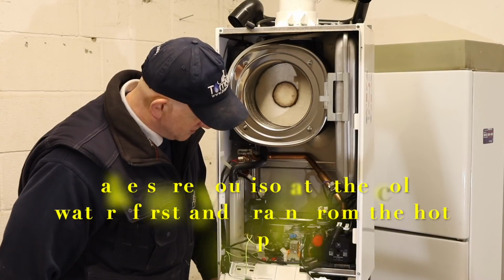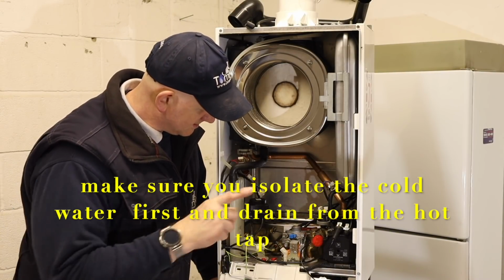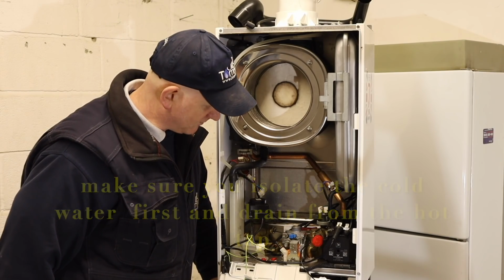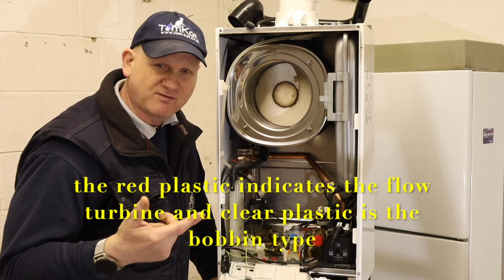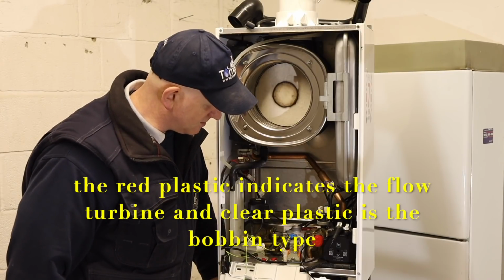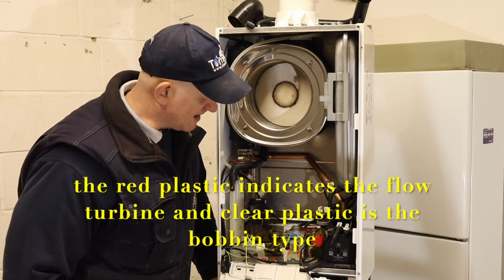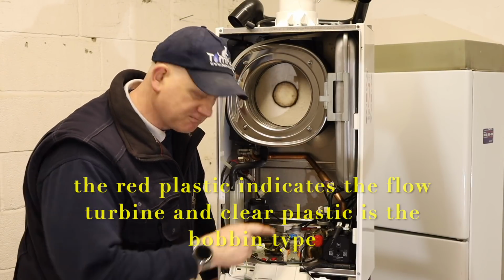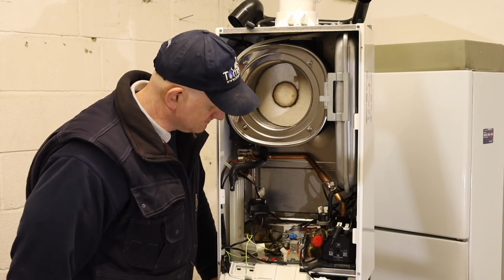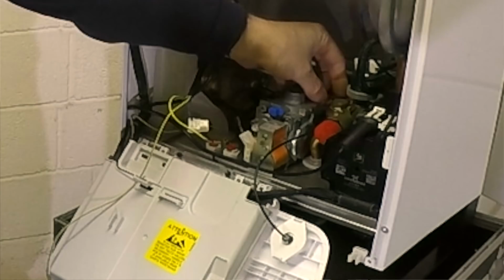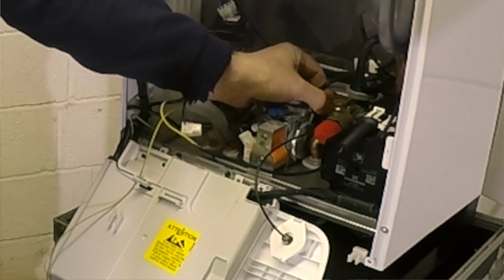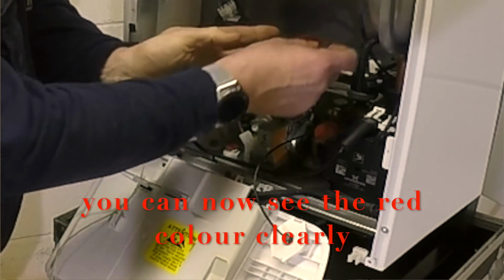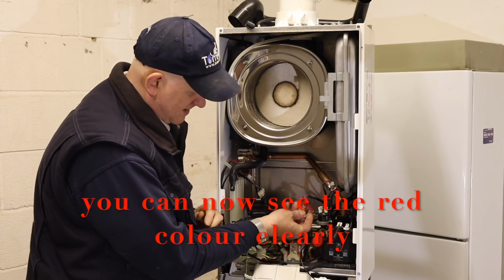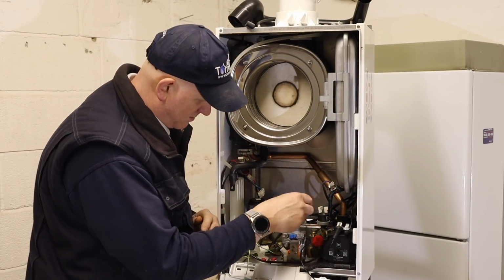has changed. So first thing we're going to do is we're going to look at the flow turbine, and we're going to take the flow turbine out and see the difference between the two turbines Baxi use. Now, this is a flow turbine rather than the bobbin type. So let's take a closer look at that then. So the first thing we need to do is actually take the Hall effect sensor off. So it just pops up, he says. So you can see now that's just popped up, and we can see that now. We'll go through that in a little bit more in a minute.